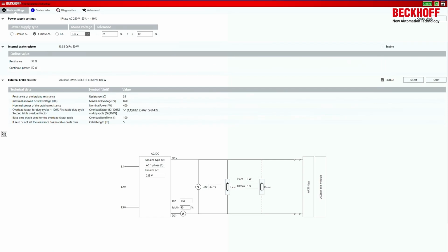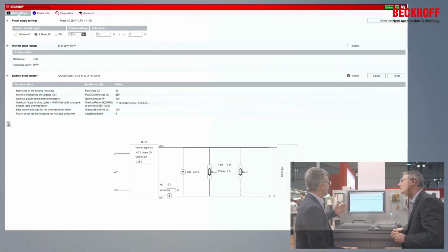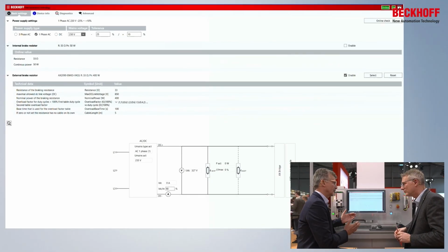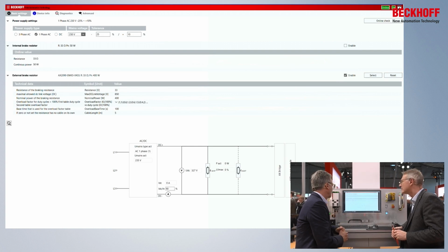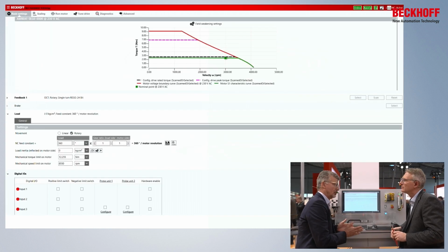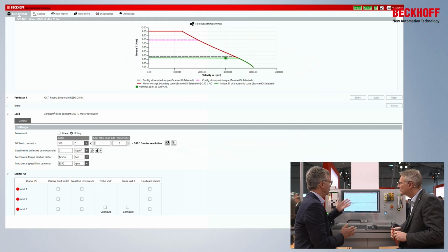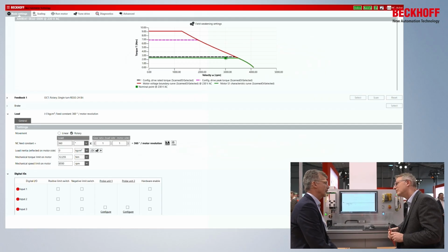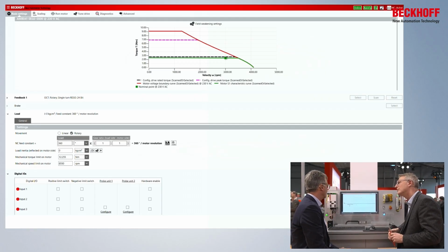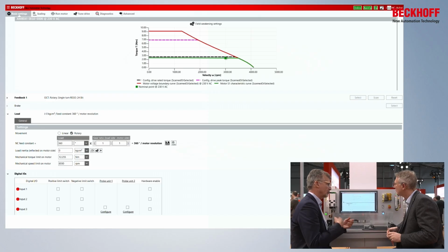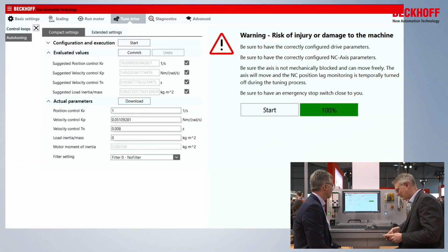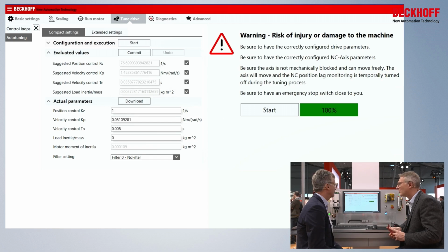Yeah. We have our drive manager for that integrated also in TwinCAT. And there we see which power is connected. If it is single phase or 3-phase, we can select tolerances for different countries, which is sometimes necessary. Select if an external or internal braking resistor should be used. And because all of our components have electronic nameplates, we also see for a specific motor, a specific speed torque curve, how the motor behaves then. We can see there what the setup is for the NC connection, if there's a specific gearing in between. But this is then the highlight of our drive manager.